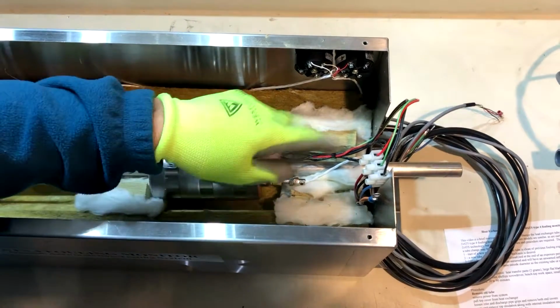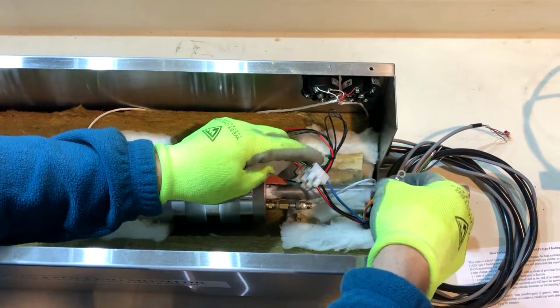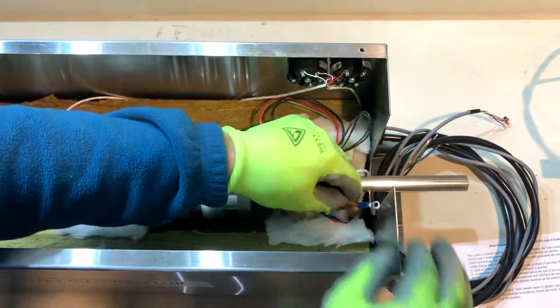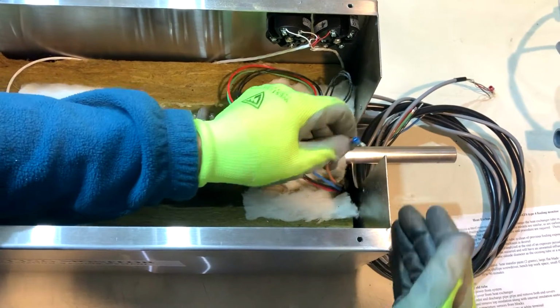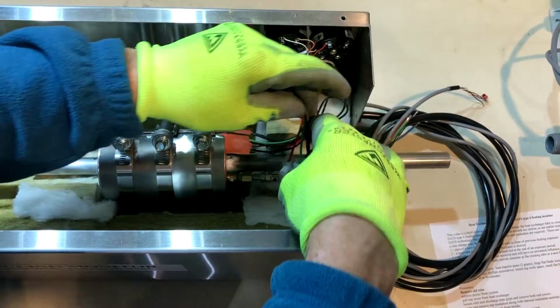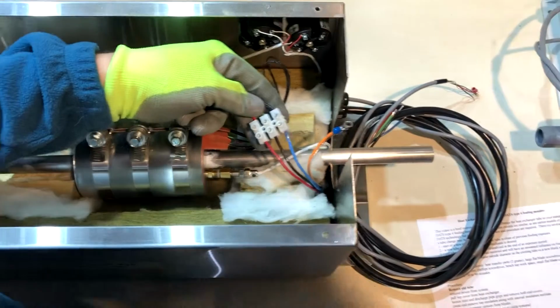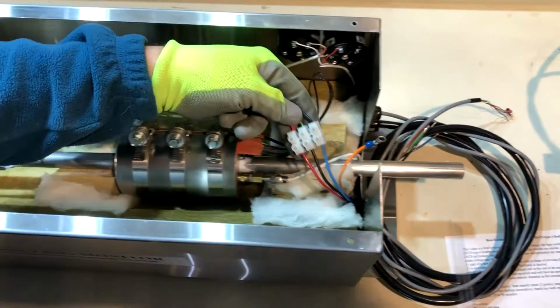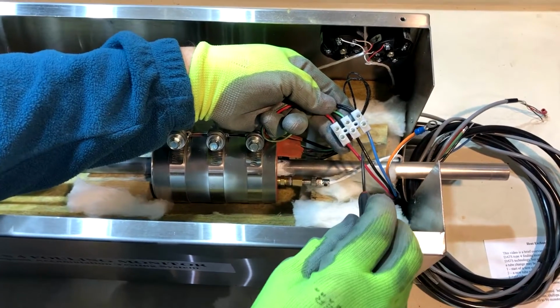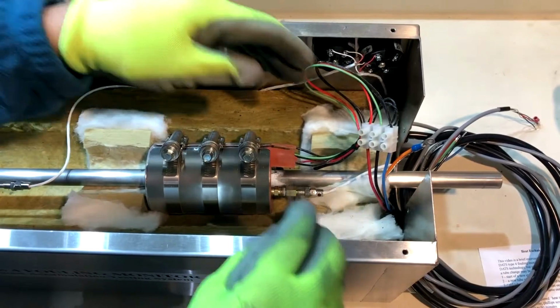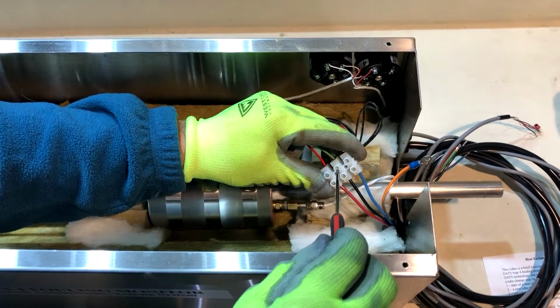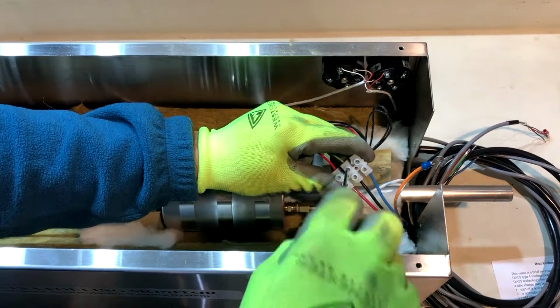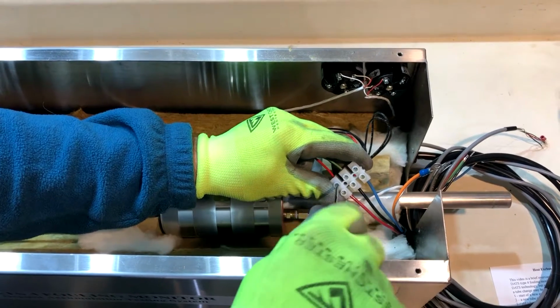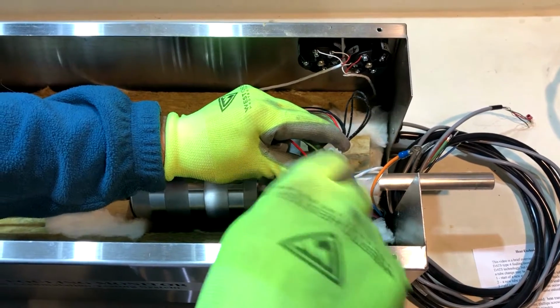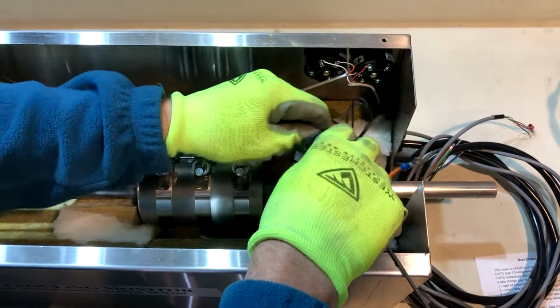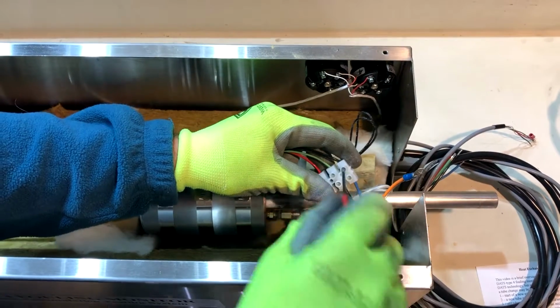Okay, so with the core of the heat exchanger exposed, we've got the power connections here and the 2 temperature sensors. Also, I want to note that there is a ground wire here that is connected, I didn't show that earlier, to the end plate, so ensure that's set to one side. The main heater power connections are taken off one at a time. You notice the ground is in the center, green on one side that goes to the heater element and black on the other side. Either side can be removed. And then the power is the red and the blue. So on 240 volt systems, they're both hot, and on 120 volt, one is hot and one is neutral.